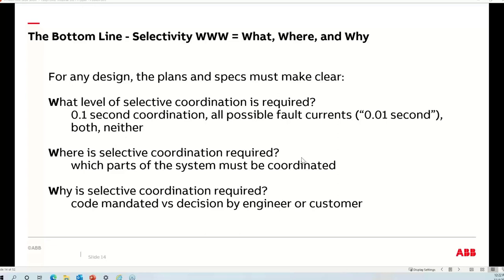The 'where': where is the selective coordination required? In many cases it is obvious from knowing electrical systems. Using labels like ATS-LS (life safety) or ATS-LRS (legally required standby) makes it easy to identify which systems require coordination. But I have seen drawings that use ATS-A, B, C, D, etc., leaving the vendor to dig through panel schedules or call the engineer. It's simply better to use N for normal, E for emergency, ATS-LS, ATS-LRS — that will more readily identify which parts of the system require selective coordination and produce an accurate bill of material.